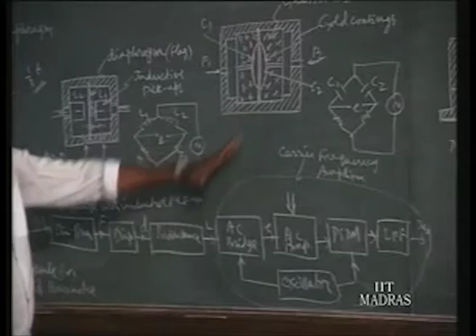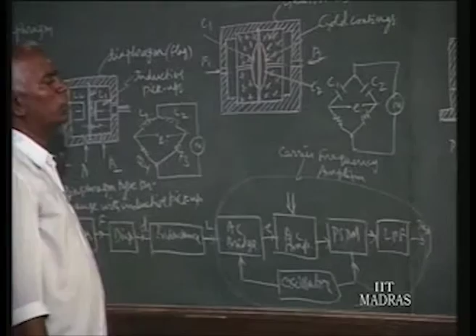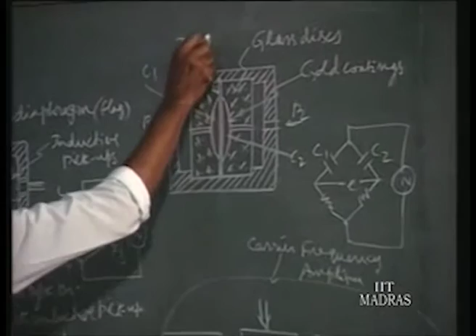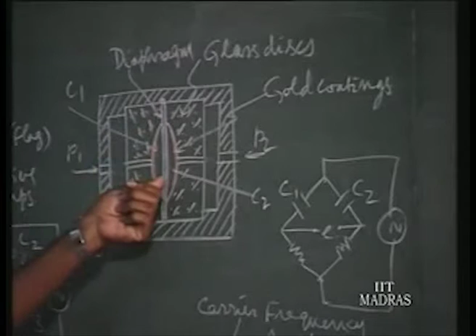Here there is another version where the deflection of the diaphragm is made use of to change the capacitance of two capacitors. This is the diaphragm, which is acted upon by two pressures P1 and P2. When P1 becomes larger, it deforms like this, so the distance changes for the two capacitors, C1 and C2. The common plate is the diaphragm, and the fixed plates are obtained by having a gold coating on two glass pieces like this. They are suitably connected by wires, and you can build a bridge network somewhat like this. This plate and this plate are nothing but our diaphragm, the same element.